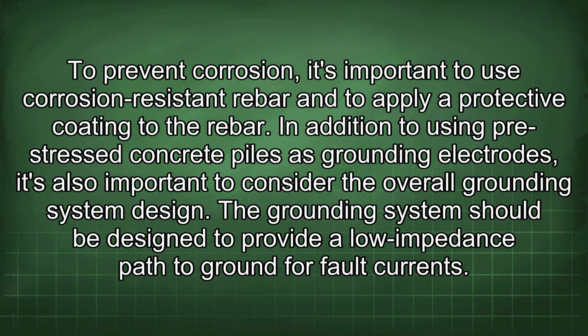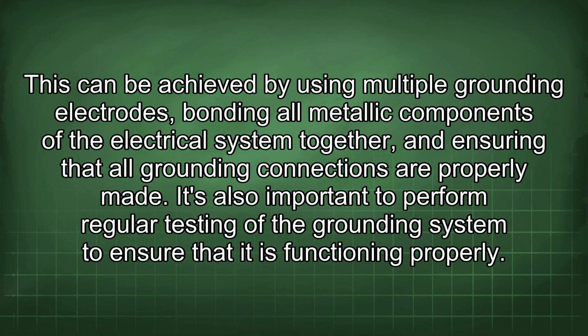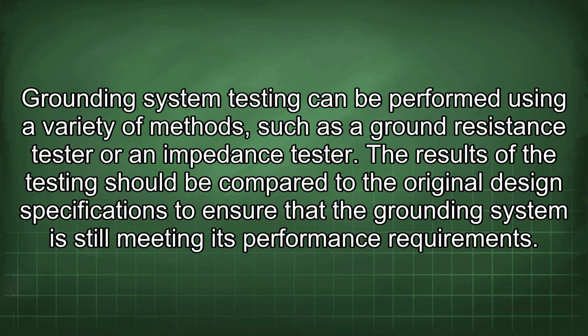In addition to using pre-stressed concrete piles as grounding electrodes, it's also important to consider the overall grounding system design. The grounding system should be designed to provide a low impedance path to ground for fault currents. This can be achieved by using multiple grounding electrodes, bonding all metallic components of the electrical system together, and ensuring that all grounding connections are properly made. It's also important to perform regular testing of the grounding system to ensure that it is functioning properly. Grounding system testing can be performed using a variety of methods, such as a ground resistance tester or an impedance tester. The results of the testing should be compared to the original design specifications to ensure that the grounding system is still meeting its performance requirements.